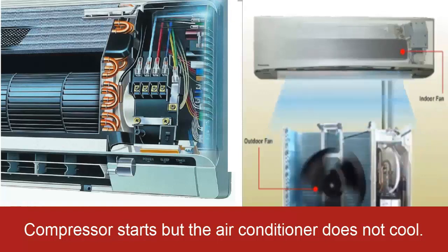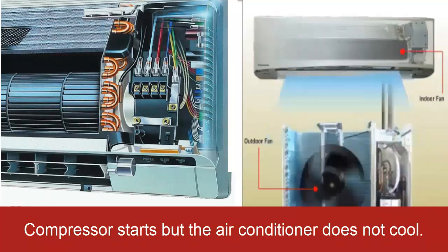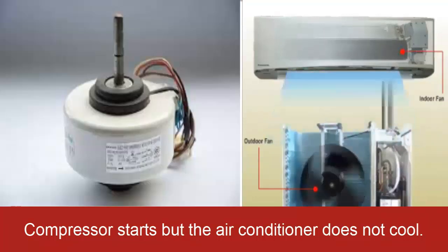5. Obstruction of the air conditioning turbine. If the air conditioning turbine is obstructed, there can be a significant amount of moisture on the coil and inadequate airflow. Maintenance of the turbine and the evaporator is essential to resolve this issue.